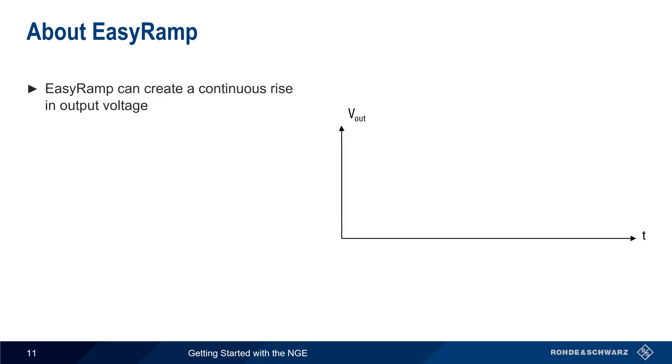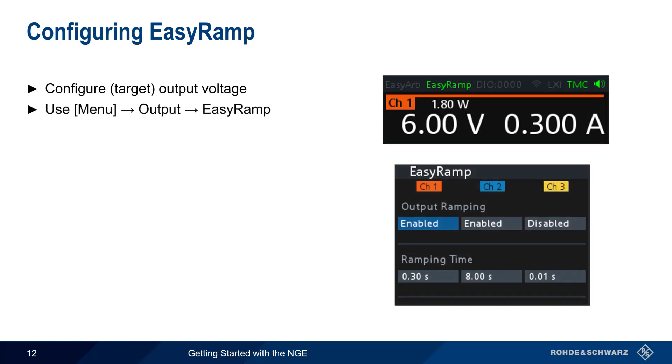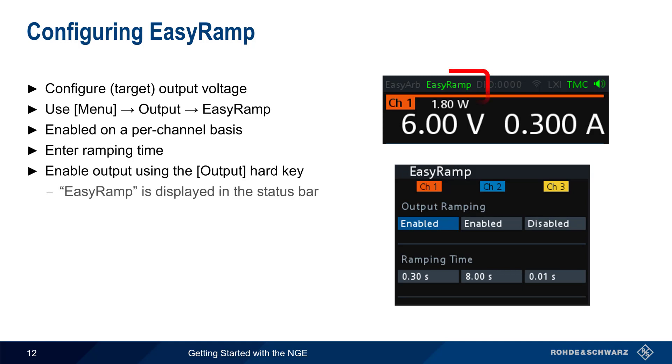As the name implies, EasyRamp is used to create a continuous rise, or ramp, in output voltage. The output voltage starts at zero and rises to a defined voltage over a ramping time from 10 milliseconds to 10 seconds, after which it remains constant. To configure EasyRamp on the NGE, first configure the final or target output voltage as usual. Then press the menu hard key and select Output EasyRamp. EasyRamp is enabled on a per-channel basis, with the only parameter being the ramping time needed to change from zero volts to the final output voltage. Once configured, the ramped output is enabled using the Output hard key. Note that EasyRamp is displayed in the status bar when configured for one or more channels.